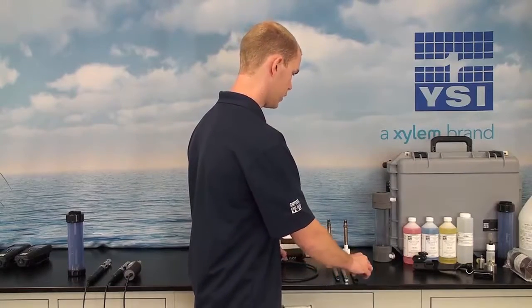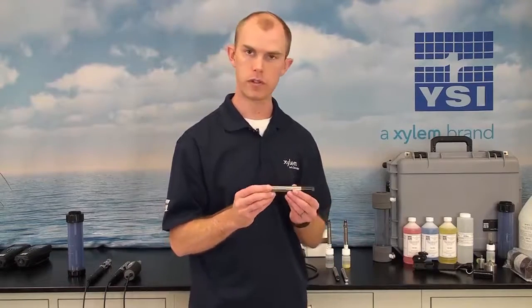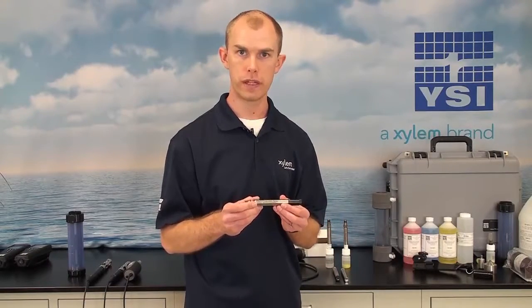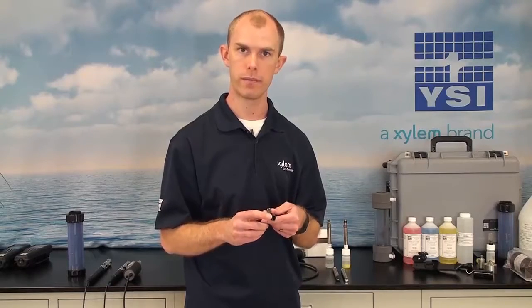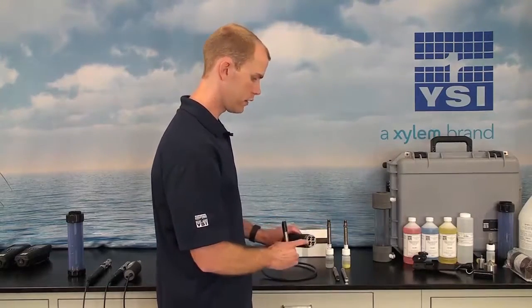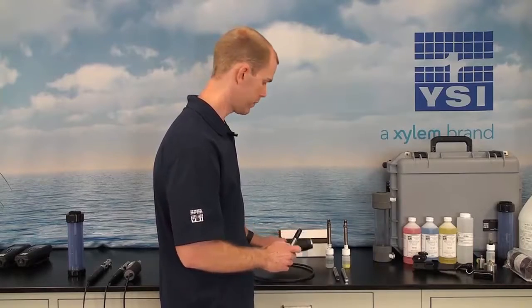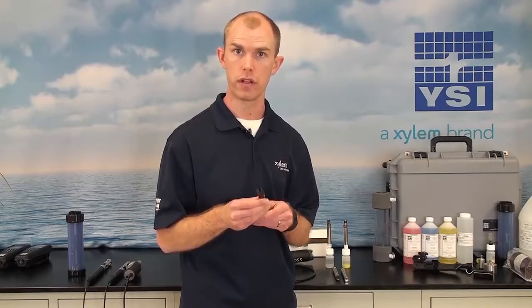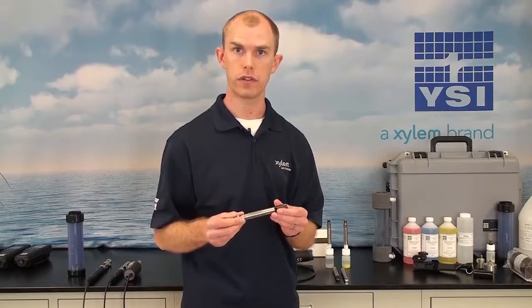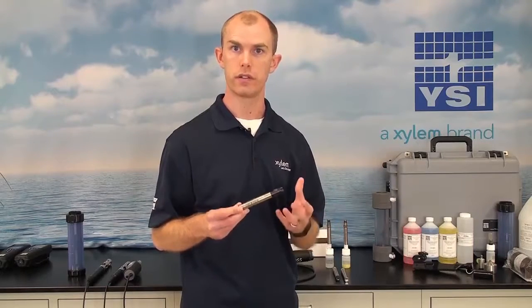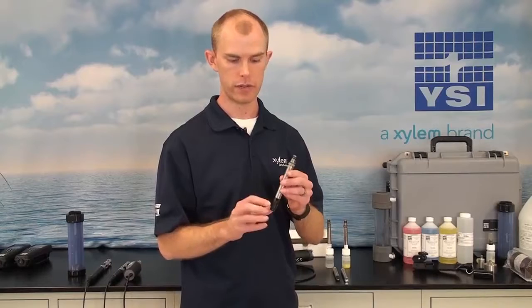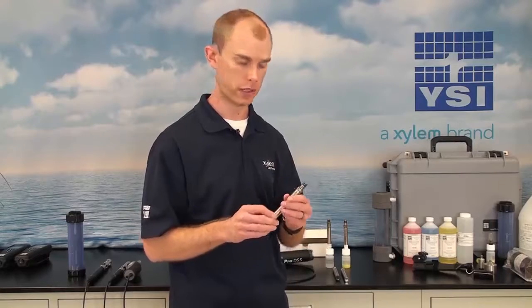The first sensor you would want to order is the conductivity temperature sensor. This is a critical sensor to order because it has the built-in thermistor here at the bottom. This ProDSS 4-port cable does not have a built-in thermistor anywhere, so in order to get accurate readings for your other measurements, such as dissolved oxygen and pH, you would want an accurate temperature sensor installed. Get the conductivity temperature sensor to ensure your measurements are accurate. It also has the conductivity cell up here for measuring conductivity, salinity, specific conductance, and similar parameters.